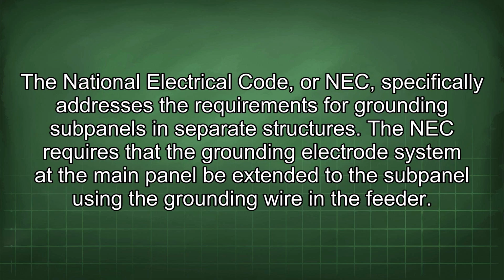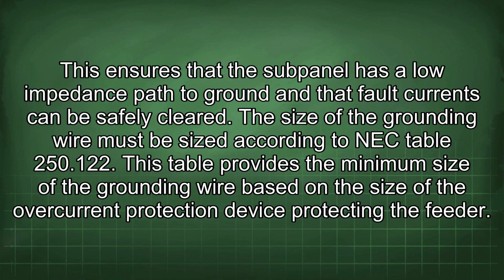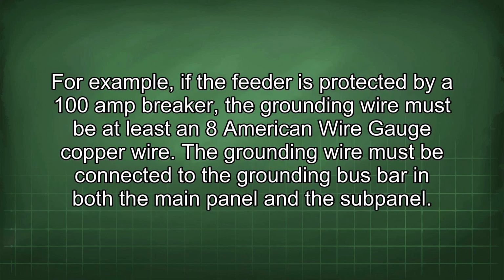The National Electrical Code, or NEC, specifically addresses the requirements for grounding subpanels in separate structures. The NEC requires that the grounding electrode system at the main panel be extended to the subpanel using the grounding wire in the feeder. This ensures that the subpanel has a low impedance path to ground and that fault currents can be safely cleared. The size of the grounding wire must be sized according to NEC Table 250.122. This table provides the minimum size of the grounding wire based on the size of the overcurrent protection device protecting the feeder. For example, if the feeder is protected by a 100 amp breaker, the grounding wire must be at least an 8 American wire gauge copper wire.